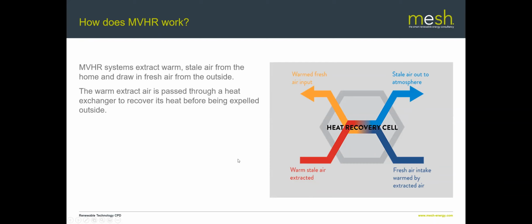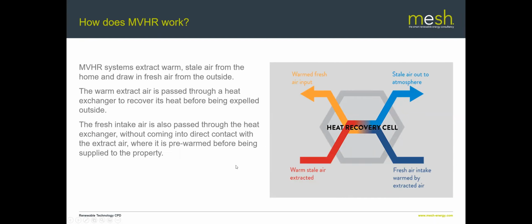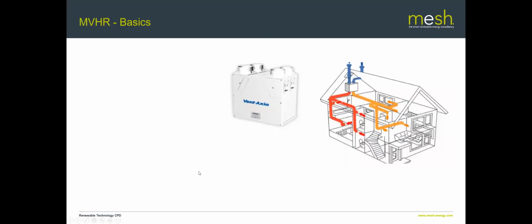So warm extract air is passed through the heat exchanger, and that recovers its heat. And these things are pretty efficient. We're talking 80% plus of the heat in that outgoing air can be recovered and reused, which can really give you quite a significant energy saving. So how does it work?